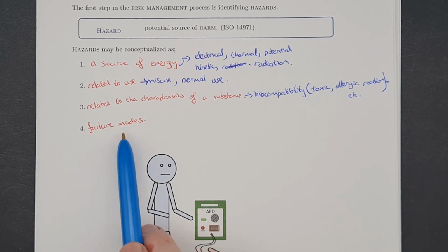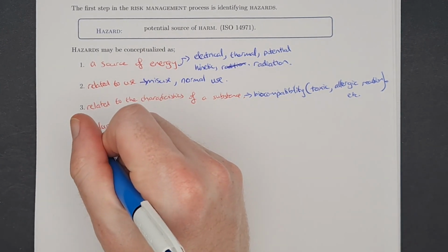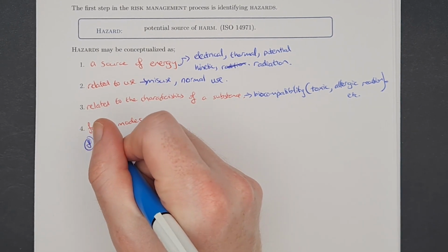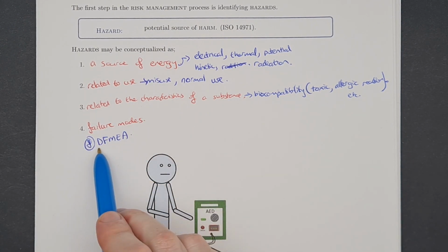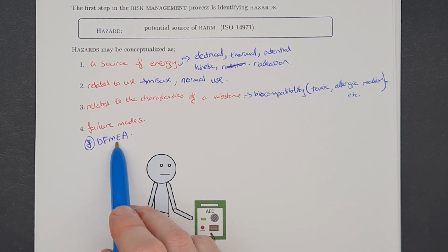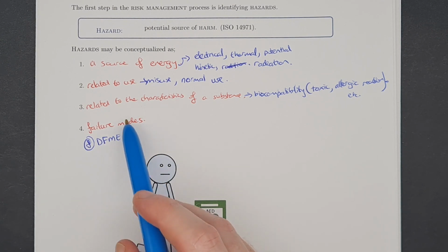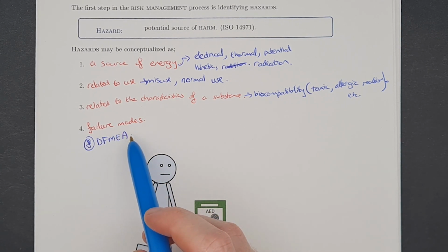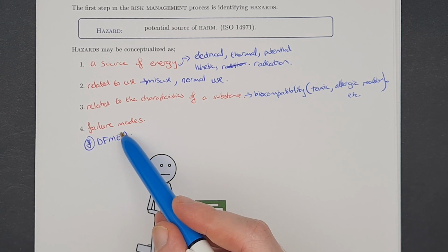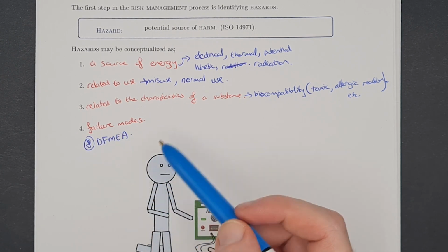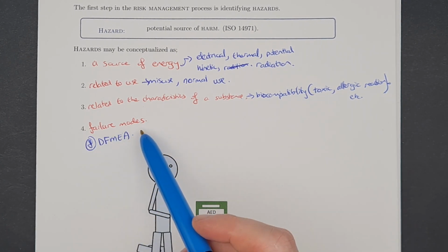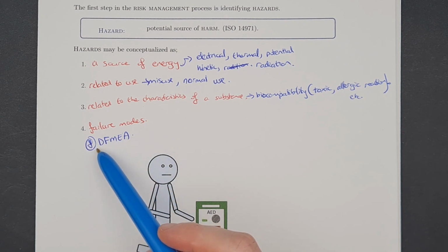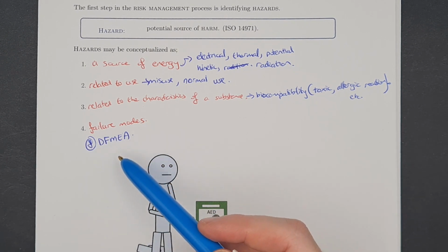And the one thing I'll mention here as well is that a lot of people use the terminology DFMEA to refer to design failure mode and effects analysis. To conduct the DFMEA, basically you look at the architecture that you've drawn out, if you can remember the architecture we drew out in earlier lessons, and you step through each item within your architecture and ask what is the likelihood of that item failing, and if it were to fail, what would the resulting harm be to the patient and what would be the severity of that harm.